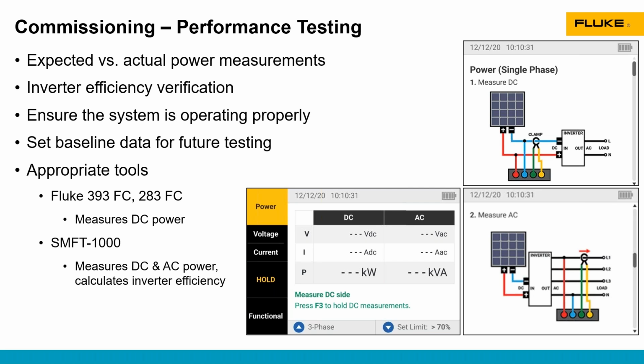At Fluke, we've got a couple tools that can measure power. The SMFT 1000 is the main one, and the screens that are pictured here are from that tool. That tool will measure power on the DC side, then it will measure power on the AC side, and it will calculate inverter efficiency between those two numbers. The limitation of that tool is that the clamp meter included with the tool is limited to 60 amps. So we would have to have an inverter with an input and output rating below 60 amps.